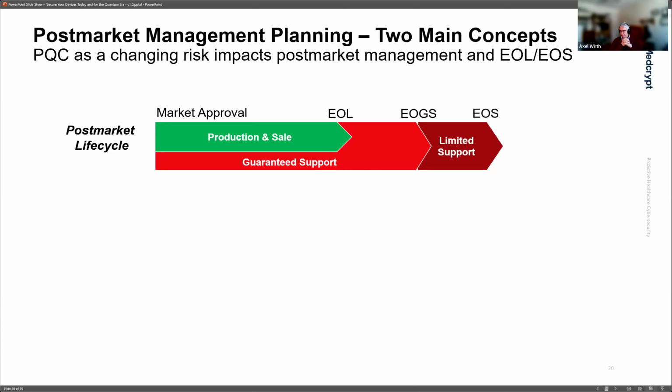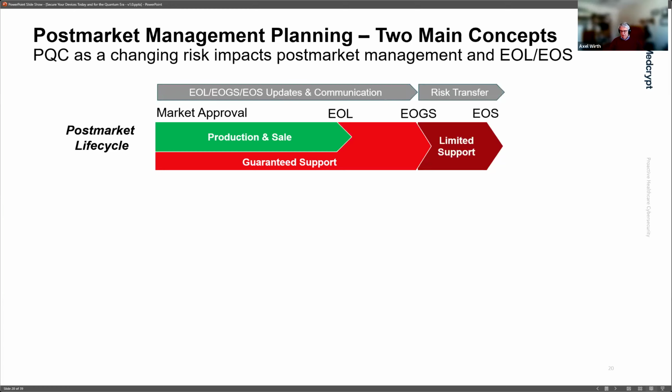Now, one thing that is important if you talk about software and cybersecurity is that your end-of-life scheme for software may be different than the end-of-life scheme for the rest of the device. What do you do as a manufacturer if certain software components are end of life, end of support from whoever your supplier is, but you're still producing spare parts for your device? Then all of a sudden, you have two separate end-of-life schemes you need to manage, and there are no general rules on how to do that because each individual scenario is different. But next, please.